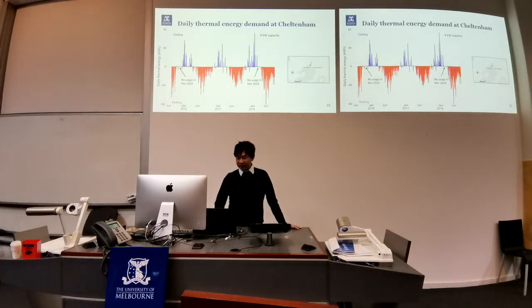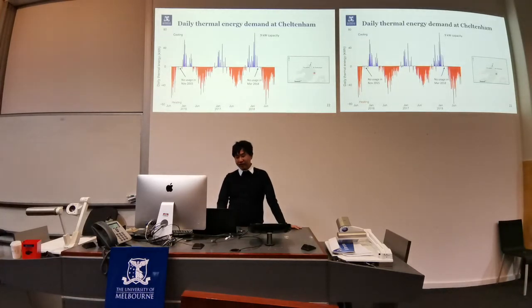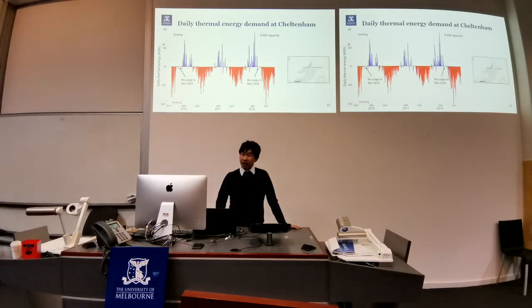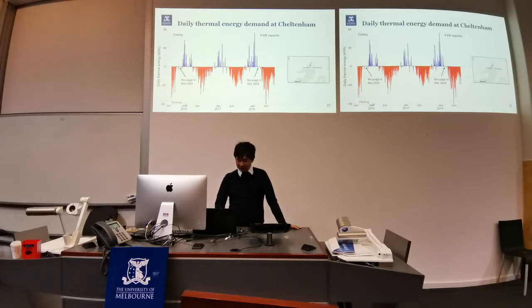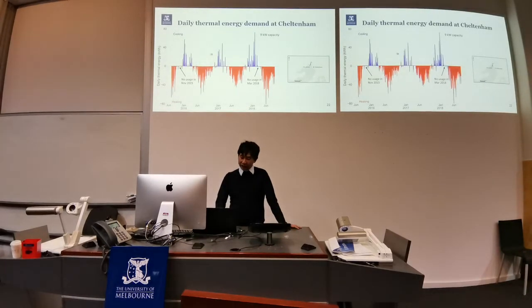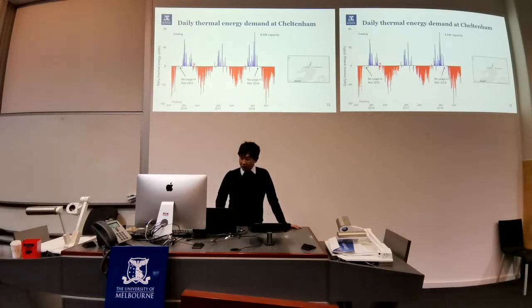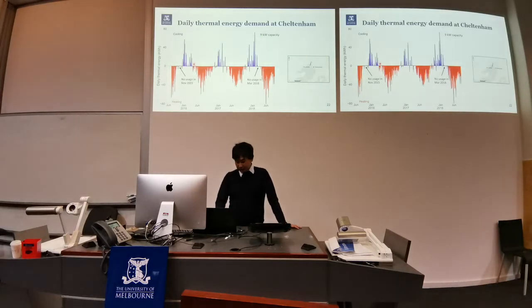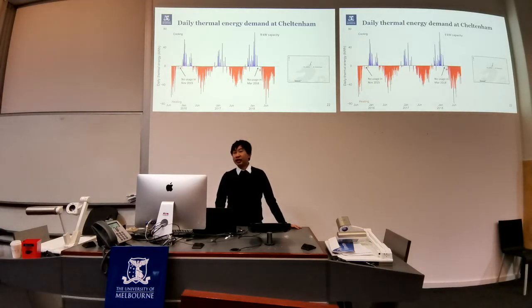Here, we have the daily thermal energy from one of the properties, as shown on this map. On the y-axis, we have daily thermal energy in kilowatt hours, and on the x-axis, monitoring time. As you can see, in this particular property, the heating use, represented by the red lines, is significantly more than the cooling use, represented by the blue lines. One observation is that the use of the system in this property is actually quite limited. As you can see in this period and that period, there are several consecutive days that the occupants did not use the system at all.